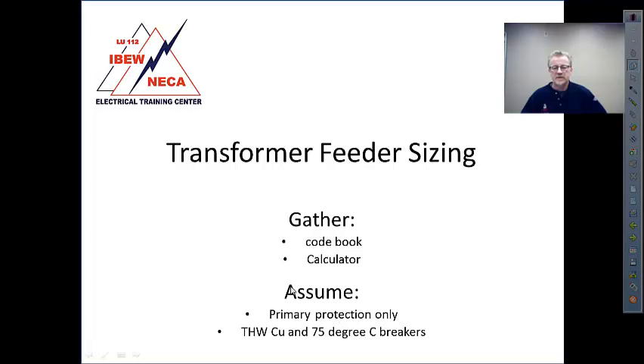We're going to make a couple of simplifying assumptions. One of them is primary protection only in accordance with 450.3(B). Also, we'll assume we have modern breakers that have 75°C termination. And also, in order to just tie in with that and not complicate our discussion of ampacity, we will assume 75°C THW copper conductors. So with that, if you want to just get started with me, we'll take a look at what it's going to take.